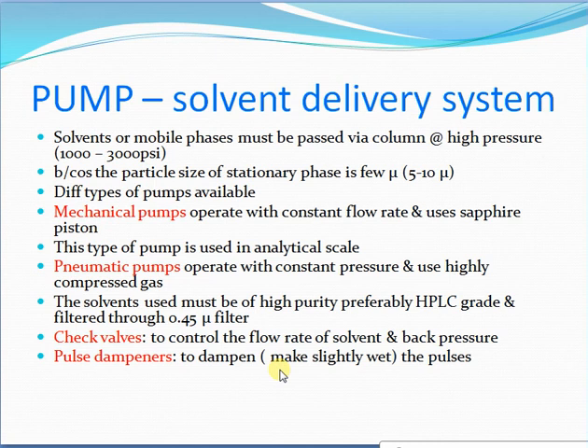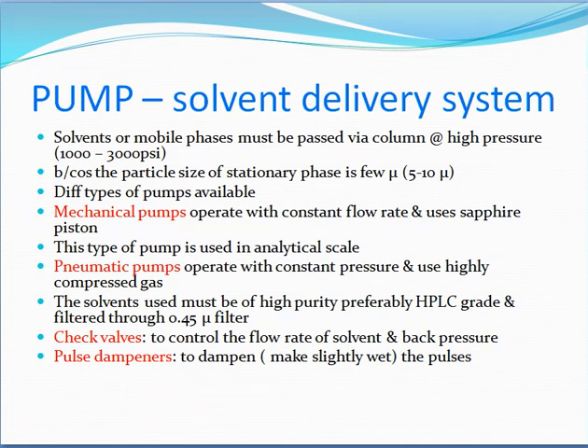Different types of pumps are available. Mechanical pumps operate at a constant flow rate and use a reciprocating piston; this type is used in analytical scale work. Pneumatic pumps operate at constant pressure using highly compressed gas. The solvent used must be of high purity, preferably HPLC grade, and filtered through 0.45 micron filters.